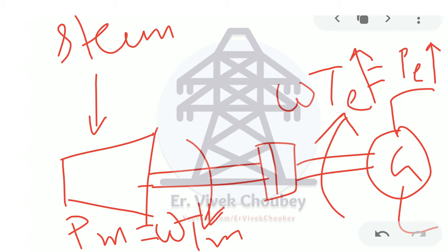So in order to overcome this effect of deceleration of the whole system, more steam is required so that the mechanical torque overcomes this resistance from the electromagnetic torque and keeps on rotating the generator, hence supplying the consumer load. So this is how the whole system works. Now, that's what we discussed till now, and we saw everything about the turbo generator system that we need here. Now, what is the problem?